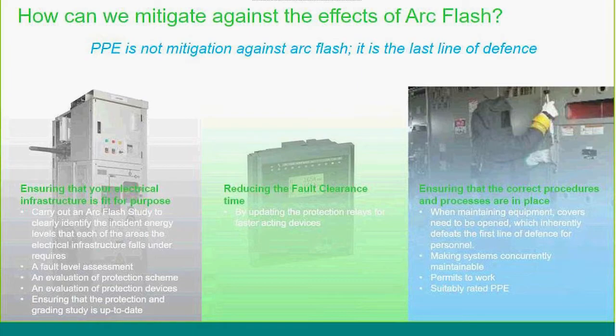So get that fault level assessment done. Get an evaluation of the protection scheme. Make sure the protected devices are functioning correctly and operating and are meeting their operating times. And make sure the protection and grading study is up to date. You have a much better piece of the jigsaw puzzle to understand how to manage that particular piece of switchgear in the substation.